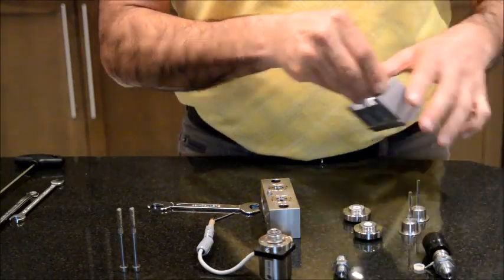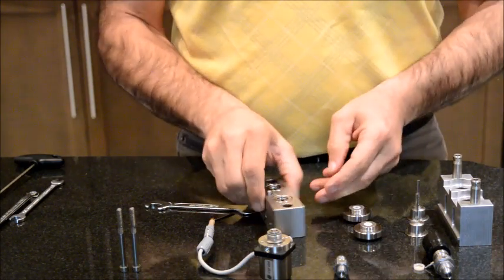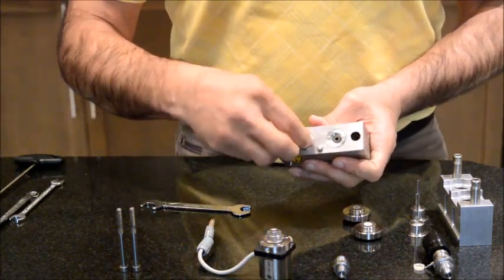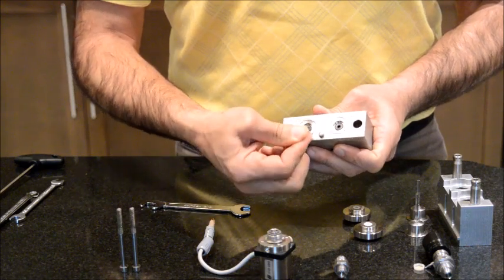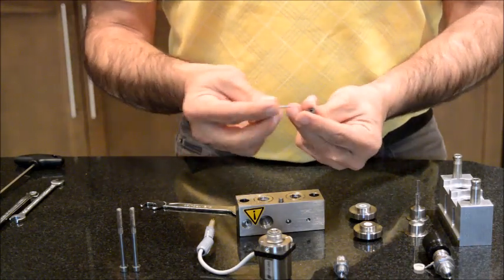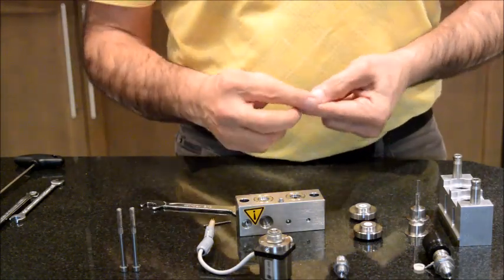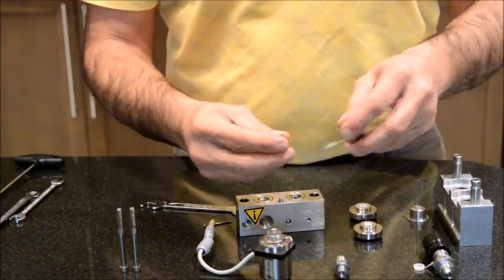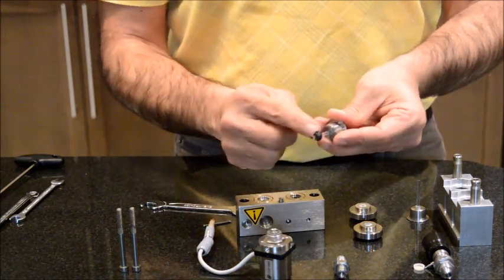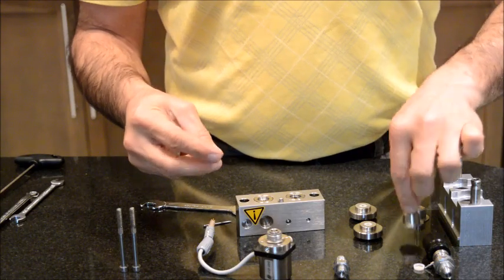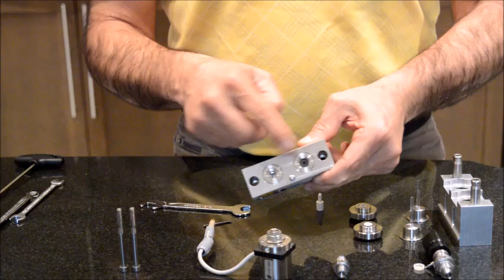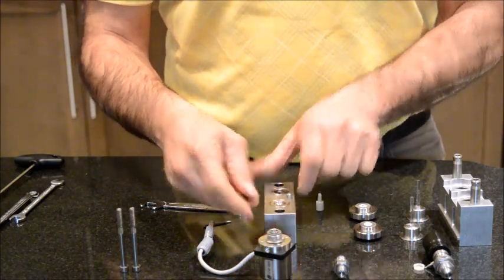These are my pump pistons and the pump seals are these black pieces inside. So over time these parts start to lose the grip that they are meant to grab the piston and the grip is gone and they start to leak. So these are the consumable again and by replacing it you will solve your leak in the pump.